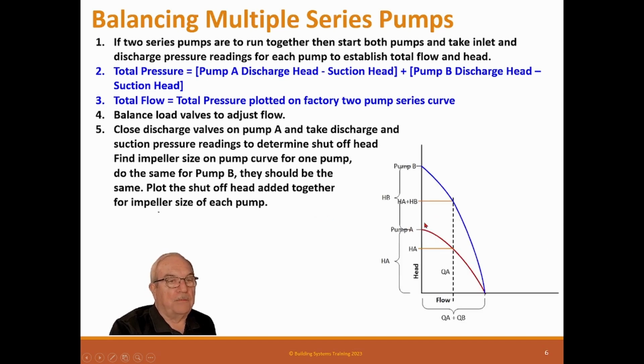So this is a 2-pump series curve. You see that this is 0 flow shutoff head for pump 1, and then you add the shutoff head for pump 2 here. So this piece here and this head here are equal. In other words, at 0 flow, the second pump does add a second pump head. But the problem is we have this curve, and this is a single pump flow at 0 head. Okay, but this second pump is the same. So this curve goes to here, and this curve goes to here. So it's the same as the other thing. It's just standing upright instead of laying down. Pump number 1 does this much head, and pump number 2 does this much head.